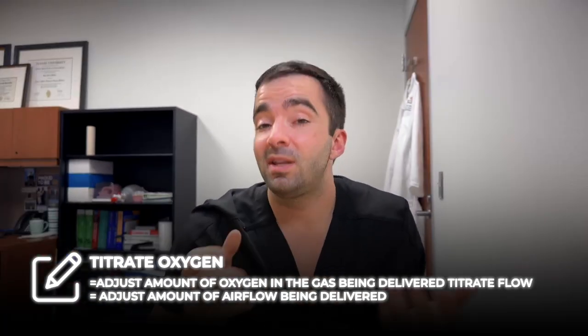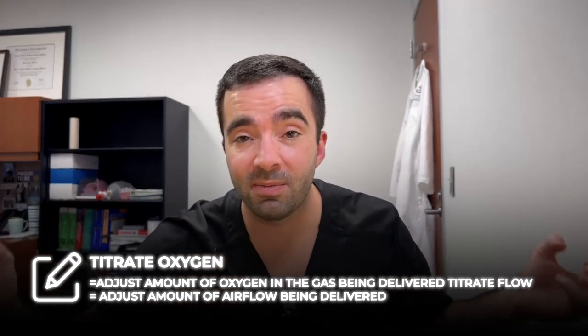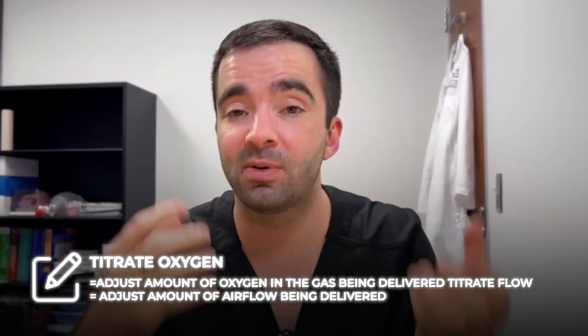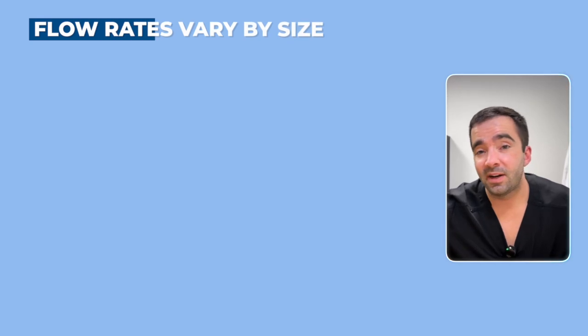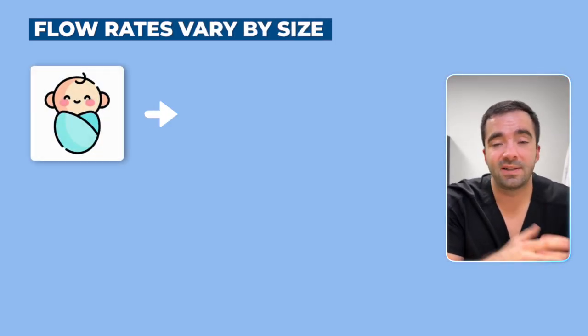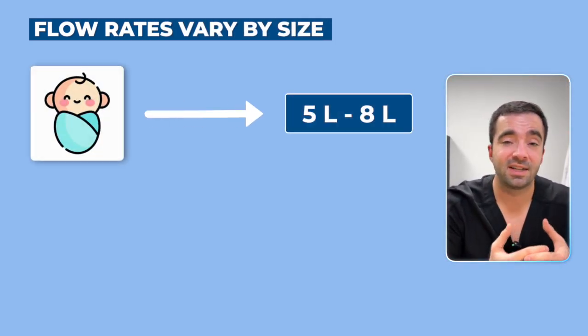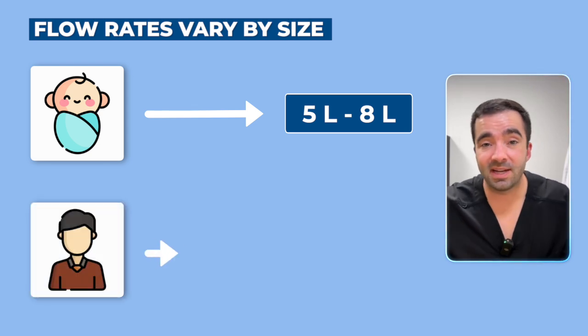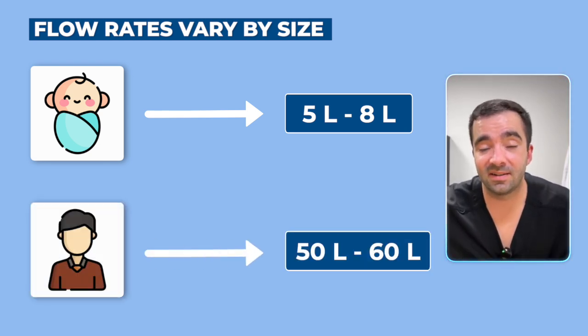And this one is nice because we don't have to just give 100% oxygen. We can actually turn the dial and decide how much oxygen we want to give. We can also turn the dial and change how much flow we want to give or how much support we're giving to the baby. The flow rates vary by size. Little newborn infants will sometimes get around 5 to 8 liters. And then the bigger you get, really big kids or people my size would be getting 50 to 60 liters per minute flow.